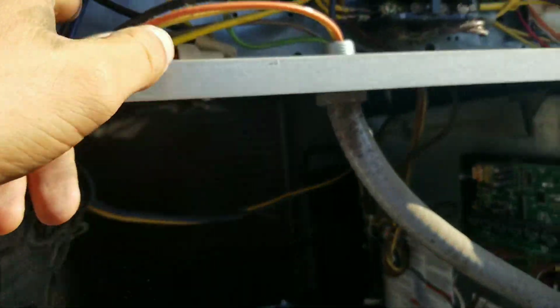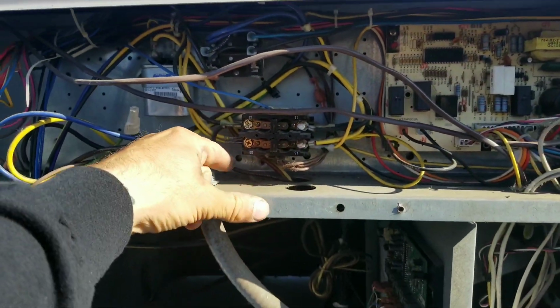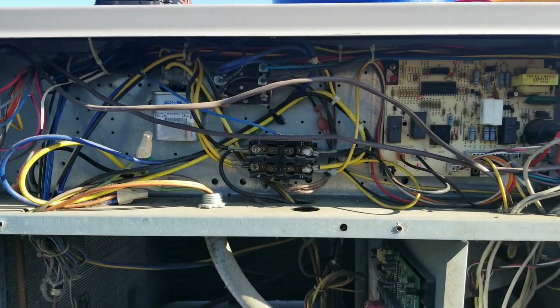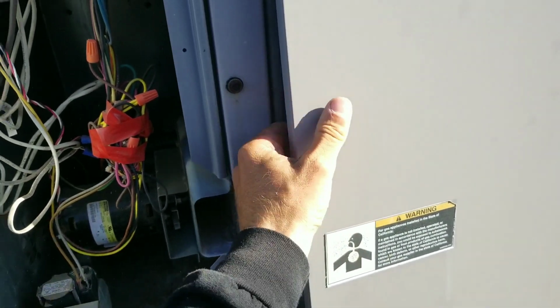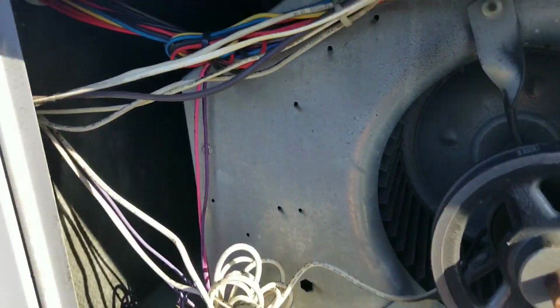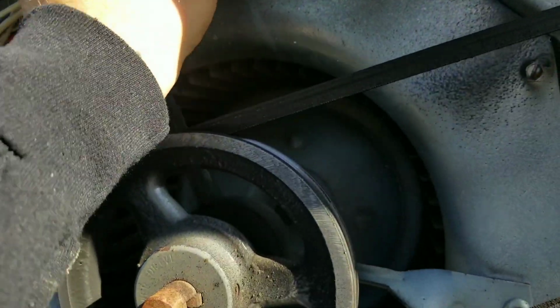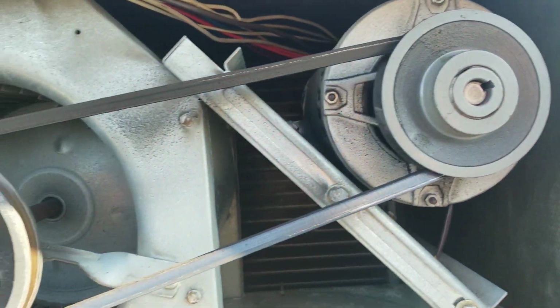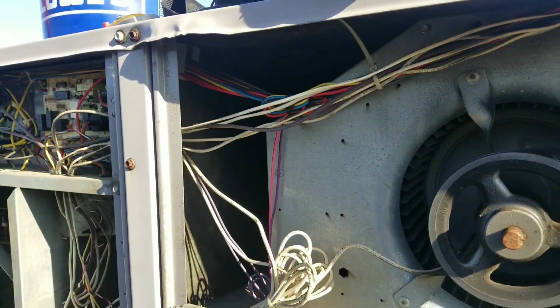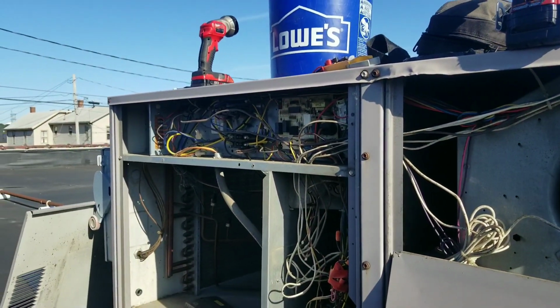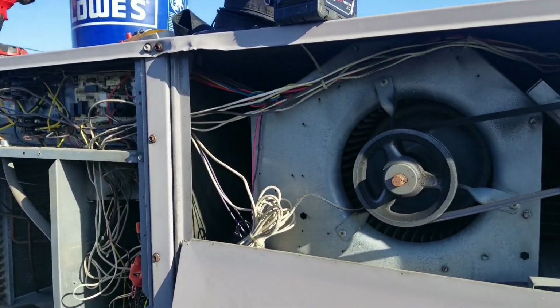What I'm going to do, though, before I do that, is I'm going to check this contactor. Because these are the wires that go to that compressor, so I'm just going to check there first to ground. So nothing over there looks obvious. Let's check here. Our blower compartment. All our wiring looks nice and tight. It's kind of hard to see back there because the sun is so bright out here, but everything looks good. Yeah, I don't see anything obvious. So let me get my meter out and start checking some components to ground, see if maybe we got something shorted out.